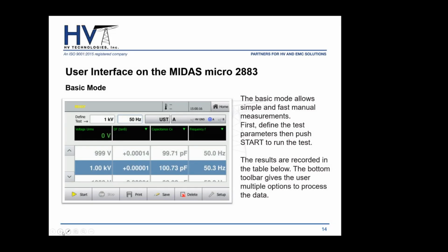When you choose basic mode, it allows for just simple, fast manual measurement. First, you will define the test parameters, and then you press start, and it will go ahead and do the measurement. As soon as it reaches a stable reading, it'll shut down the high voltage, and the results will be recorded in this table below. So in basic mode, you already have a sense. Maybe you want to test the capacitance high voltage to low voltage winding, so you know you're going to use a UST.